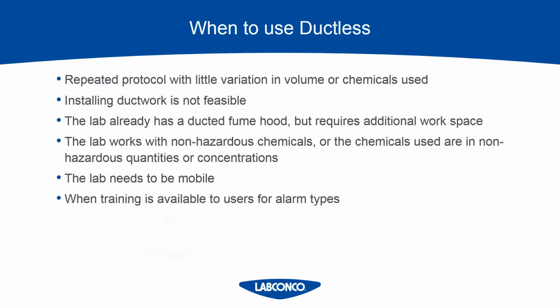If the lab already has a ducted fume hood but requires additional workspace, that's a perfect application for a ductless hood. If the lab works with non-hazardous chemicals or the chemicals are used in non-hazardous quantities or concentrations, that's a good application. If the lab needs to be mobile, like moving in the near future, renovations, temporary spaces, any of those type of things, it would benefit you to go ductless because they're easier to move. And then the last item, when training is available.